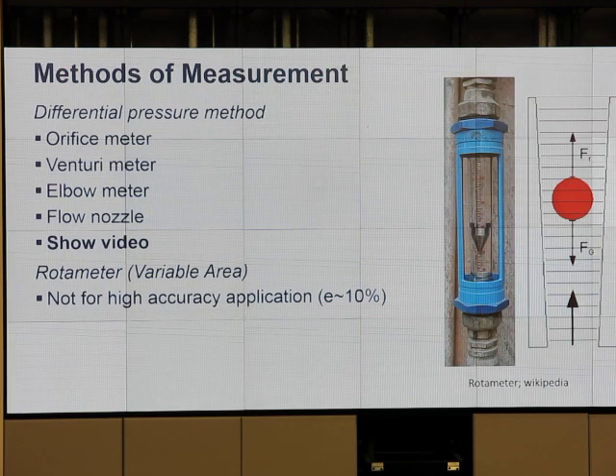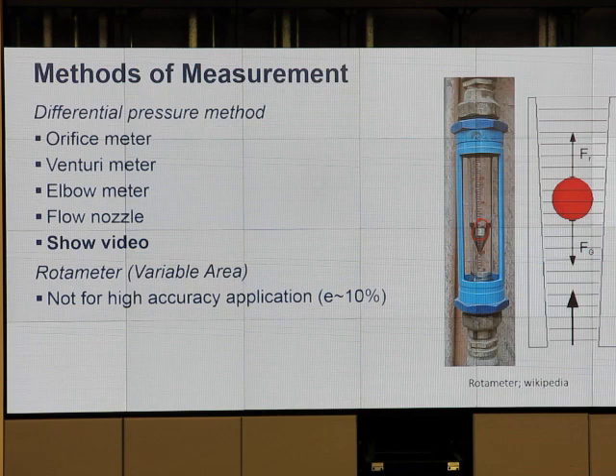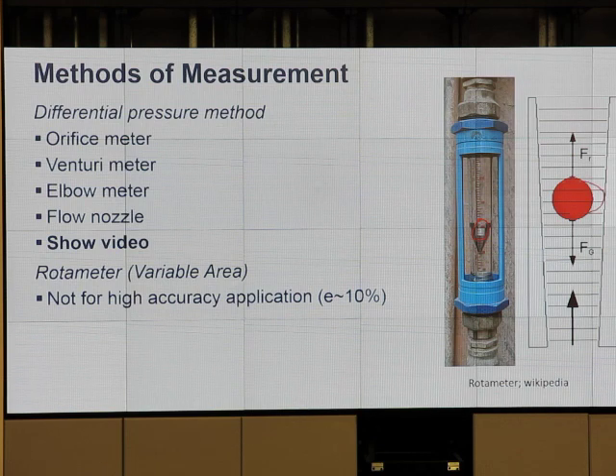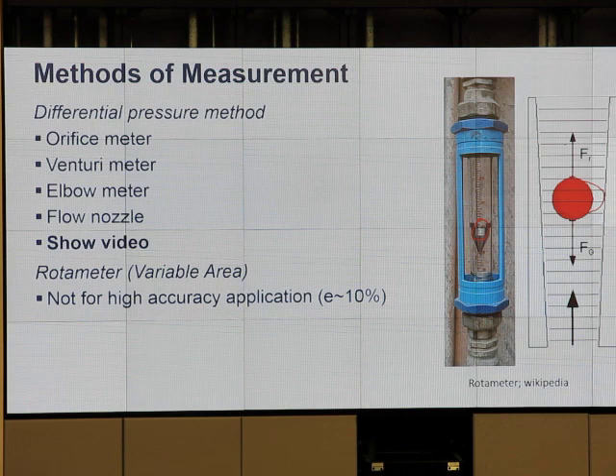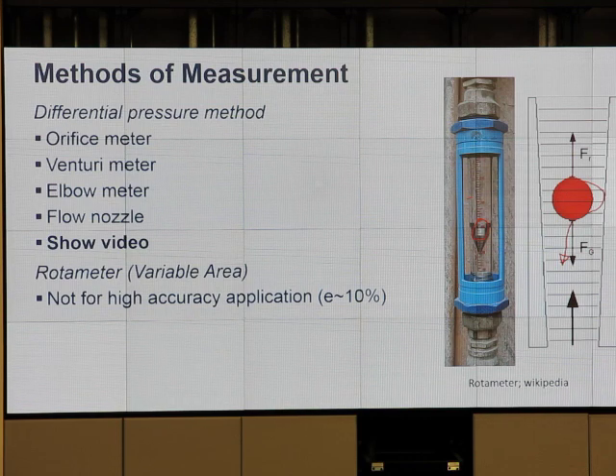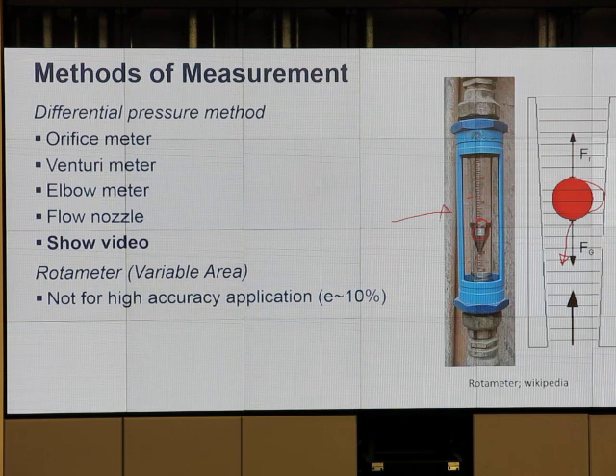The rotameter has a ball inside a tapered tube. Flow lifts the ball upward while gravity pulls it down; the equilibrium position indicates the flow rate. This measures gas flow rate, but it's not high accuracy — it's okay, but most of the time we need to know more precisely. It may be usable near surface pressure conditions.